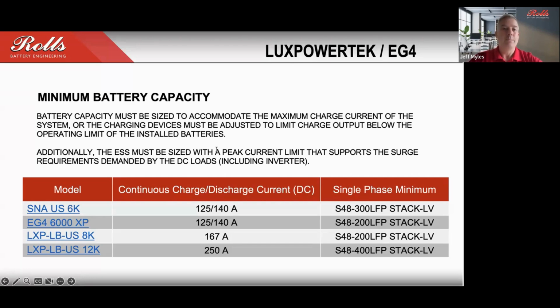And so we've outlined that at the beginning of the setup guides for each one of the inverters, to basically give you a heads up that if you do connect a smaller stack with that larger inverter, the peak discharge or potentially the continuous charge and discharge may exceed the capability of the BMS. And so it would actually trigger the BMS in those units just to shut off. So in that case, it would log it as an error, but ultimately the system will go down because it is undersized on the storage side to work with that particular inverter.